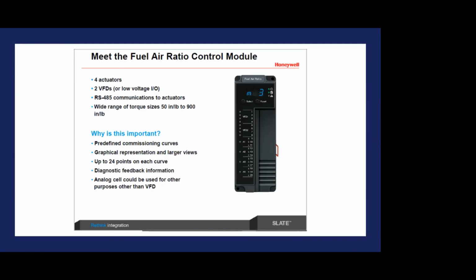It allows you to use these modules to their fullest extent based on the density of the IO that they have. Another feature, if you can see at the top there, we have VFDs. We have outputs that are dedicated to variable frequency drives to drive our combustion blowers. 4 analog outs, so we can do dual fuels with FGR along with the air. This is a very, very robust module here for your fuel air ratio control. So right now, you pop open a panel, you've got the old blue box there, and now you've got some single loop controller handling your fuel air ratio control. We can do that all now in this module, same platform, right?